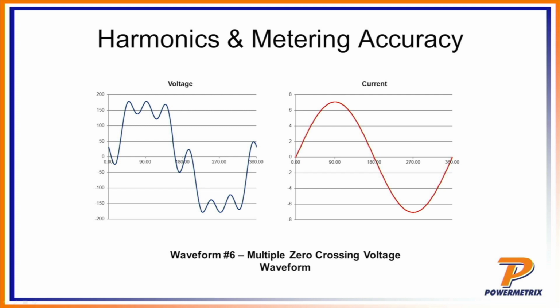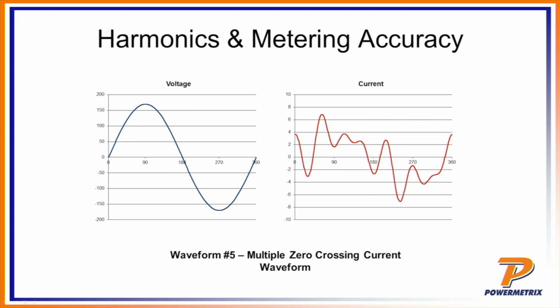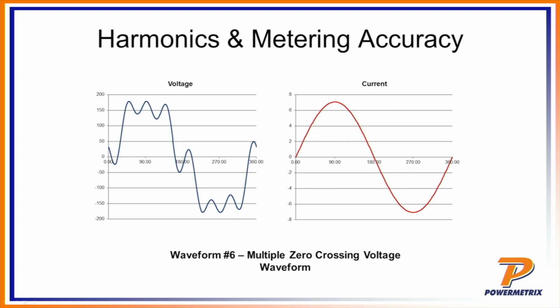The last waveform is basically multiple zero crossing, but that's on voltage, not current. And so as such, now I've gone from a nice clean voltage to a square wave looking voltage. I mentioned earlier that you might see that coming out of a cheap AC inverter, but the current is now sinusoidal. I'll be honest with you, I don't know of any real world waveform that would give you a really ugly square wave voltage input and a nice clean current output. I think you'd probably get more of a combination of both the current waveform and the voltage waveform. Nonetheless, the fact that you've got multiple zero crossings on your voltage, that's still going to cause some meters to get confused and give very bad results.